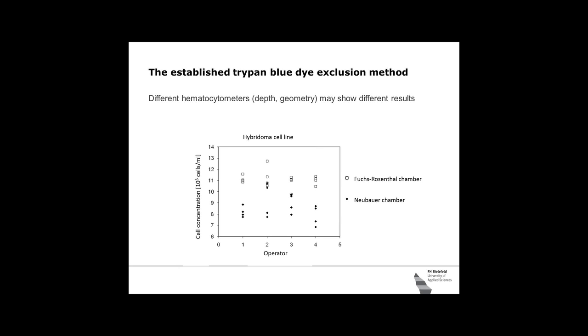But if you look at cells that are 15, 20, 25 microns in diameter, and if you have a chamber that is 100 micrometers in depth, there are rim effects, because the cells are not actively going into the chamber, they are driven by adhesive forces into this tiny slit under the chamber. So there are rim effects where there's almost no movement of liquid. And if this rim is like 20 microns at the bottom and the top of the chamber, that is 40 microns, so 40% in case of the Neubauer chamber, and it's only 20% in case of the Fuchs-Rosenthal chamber, because simply the depth of the chamber is different, and that may cause deviations. But to be honest, I don't know if that's really the case. It's only something to try to explain this.